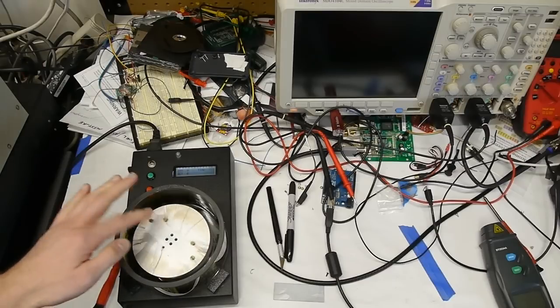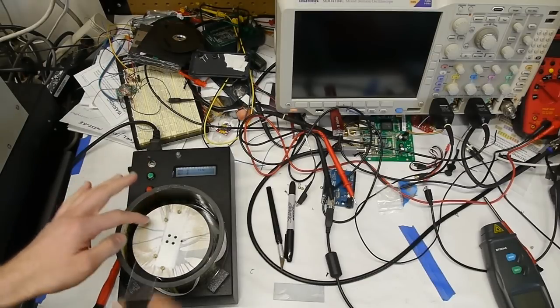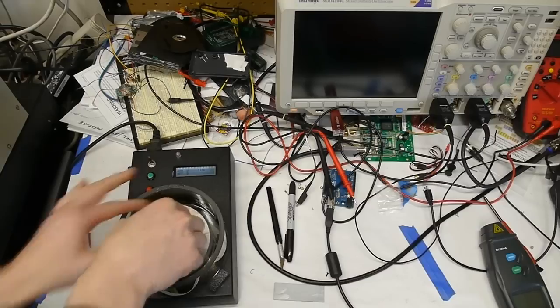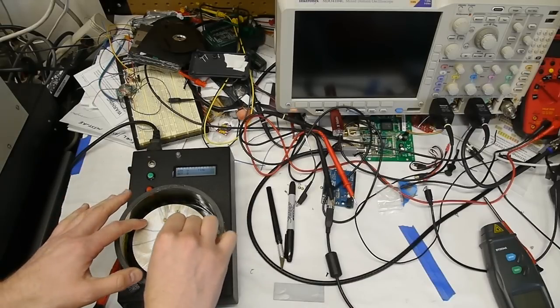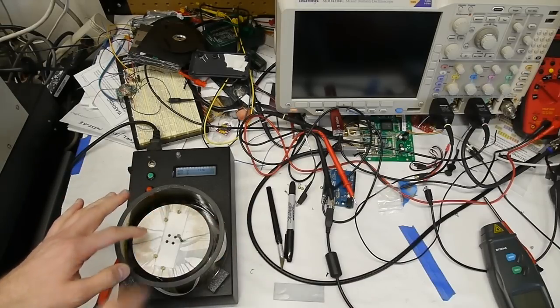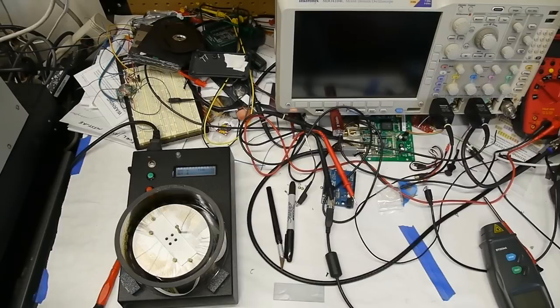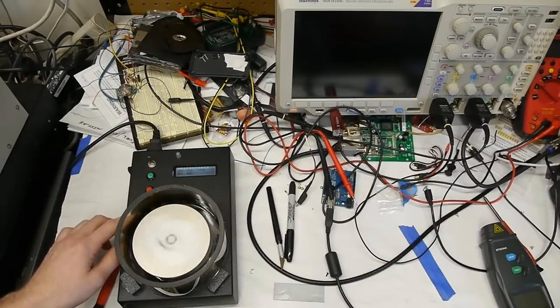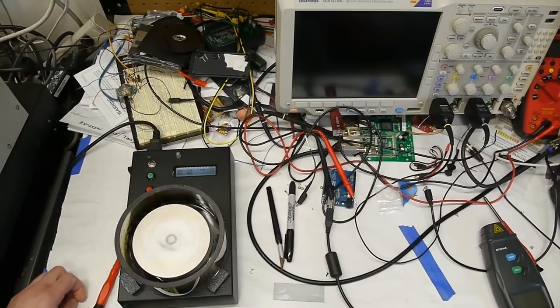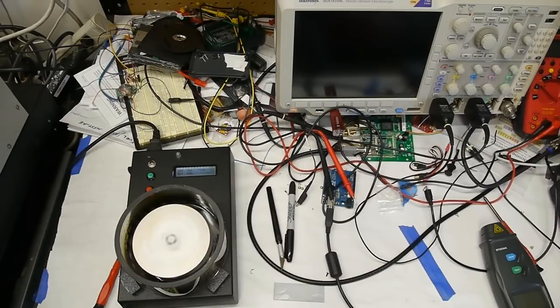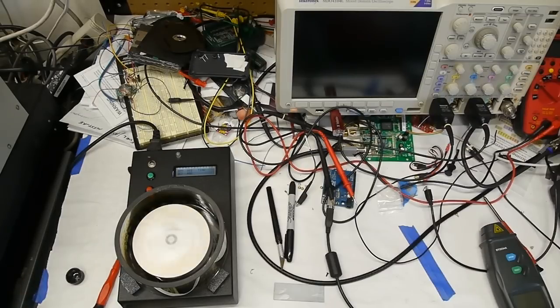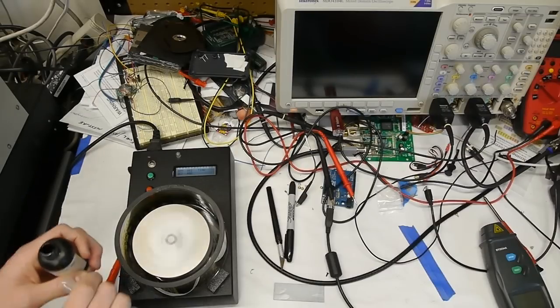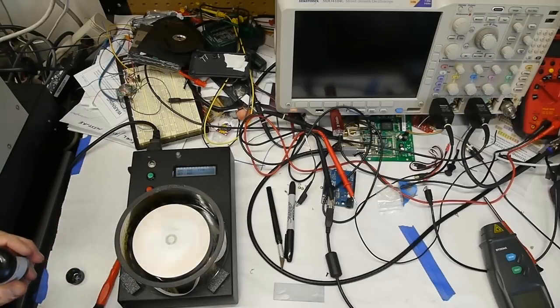It's got a rotor here, and I've put flathead brass screws in here so that when I slip a microscope slide in and put one more screw in, it holds it down and keeps it from moving on the rotor. So I'll press the green button, and it spins at about 400 RPM indefinitely. The idea is that you want to put a liquid onto the spinning slide, and the spinning motion of the spin coater will fling the liquid out and make a very even coating on the slide.